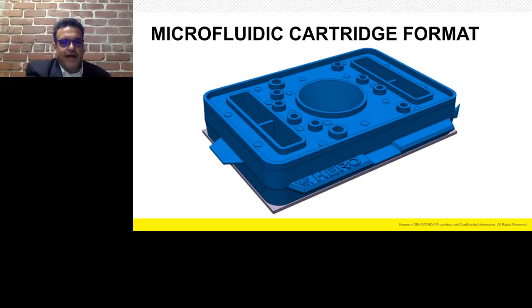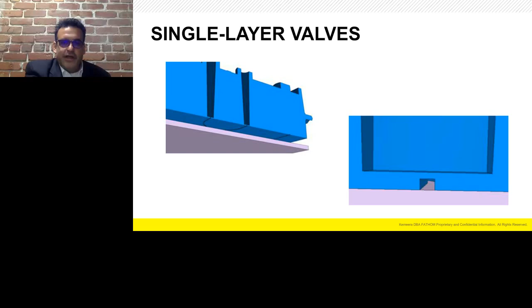Other innovations are this chip to cartridge to world interface. So normally, as I mentioned with microfluidic devices, when you have a microfluidic device like this, see these little tubes running out in the picture to the left, each one of those has to be plugged into the device manually by the experimenter when we're setting it up, which is a real pain. This allows us to hook up all the connections at once, just like you would on a computer. We also have ports that allow replenishment or emptying of the sampling reservoirs. This is what's shown on the right.